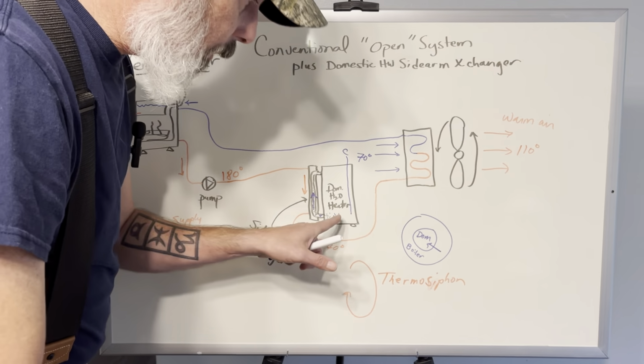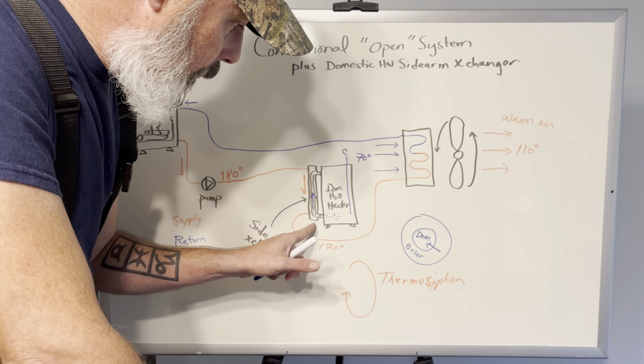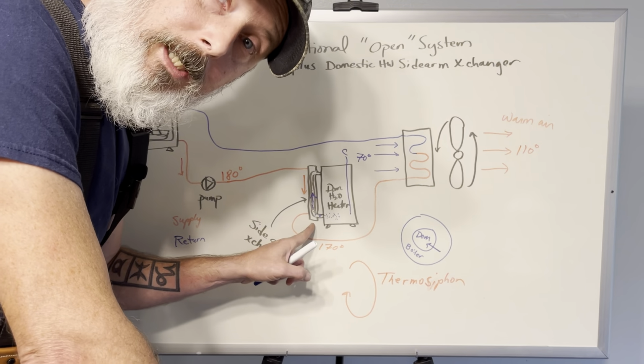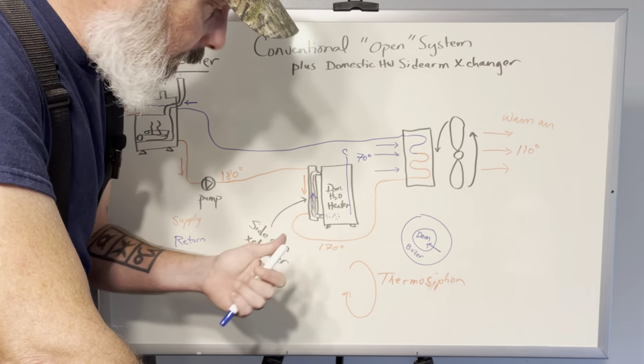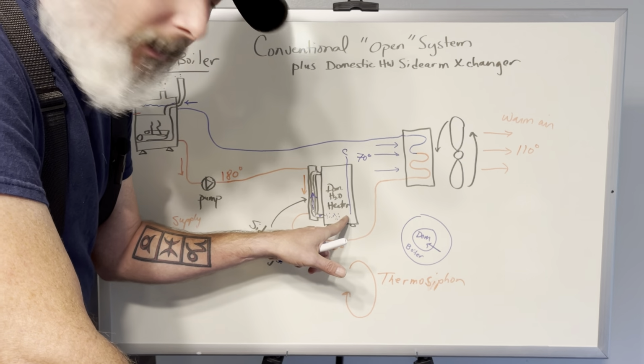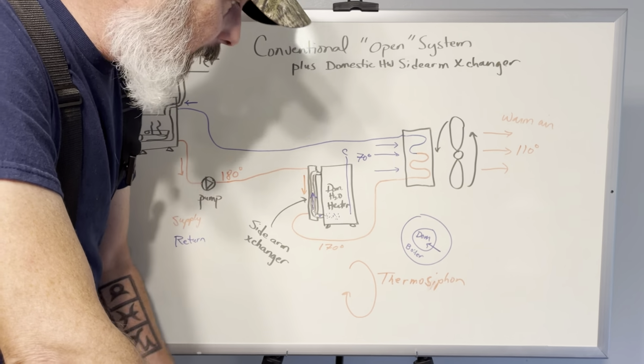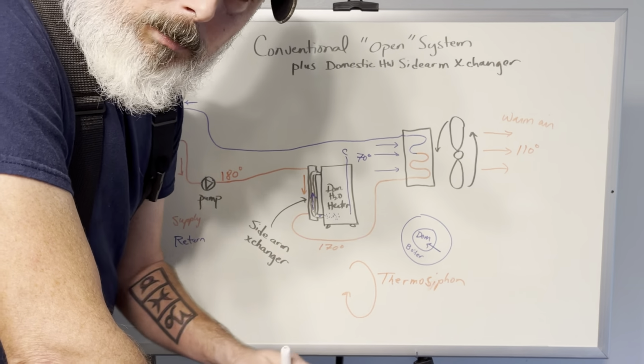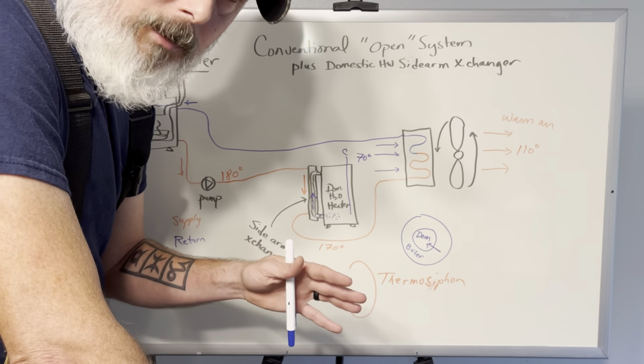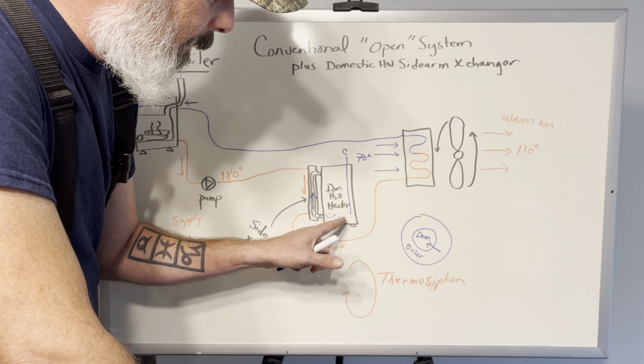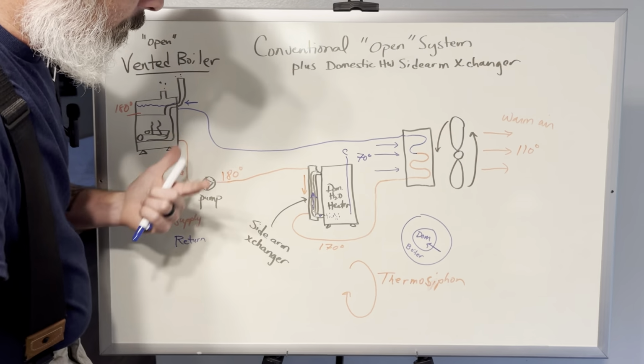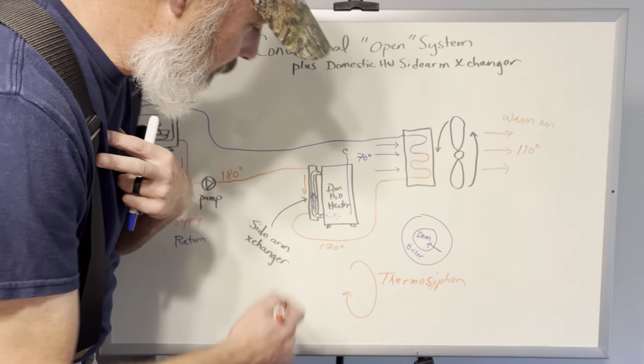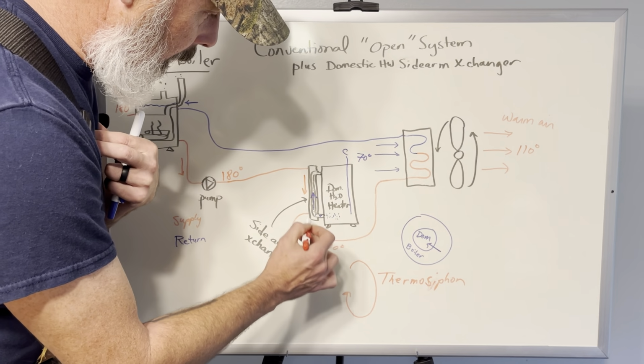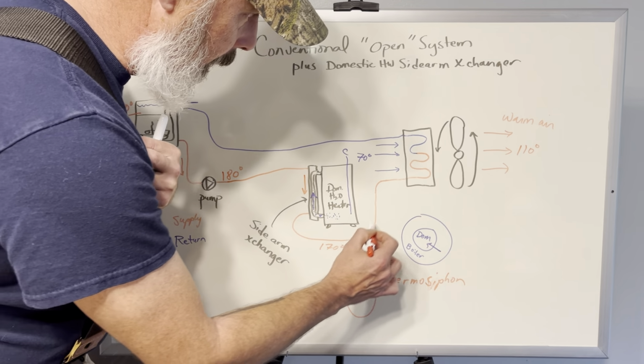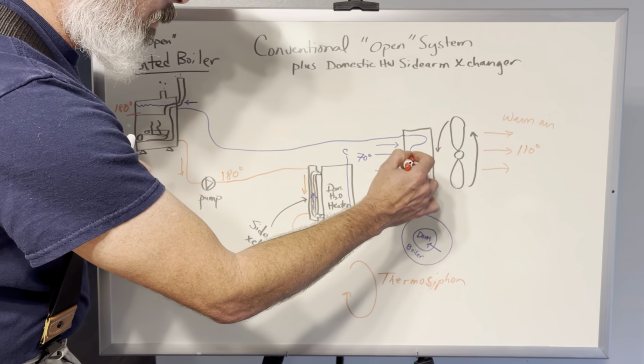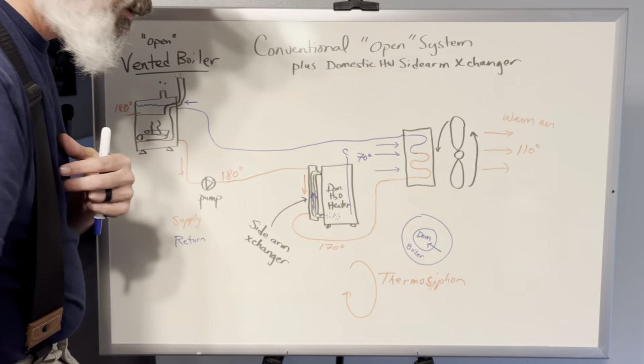So depending on how big your water heater is, depending on the capacity of your heat exchanger, depending on how hot your boiler water is, it'll recharge it over time. And obviously when you start taking showers, you're going to deplete that water just like you would normally, because that sidearm heat exchanger is not going to recover that fast. But there's a benefit to a sidearm heat exchanger. But yeah, hot water from the boiler, my recommendation, come in the top and have the outlet on the bottom, and then it will carry on, go to your forced air coil, through the coil, it'll give up heat, go back to the boiler to be reheated.